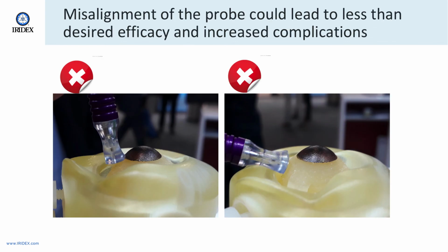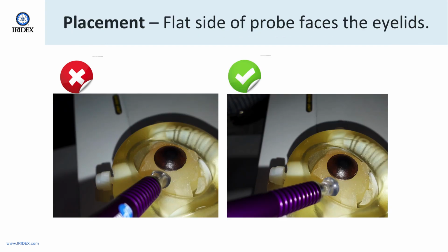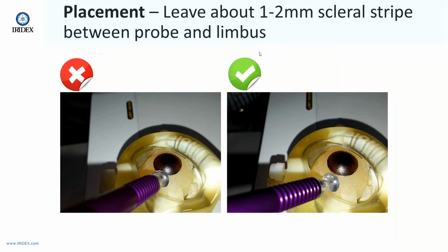Misalignment of the probe could lead to less than desired efficacy and an increase in complications. Orientation or placement puts the flat side of the probe towards the eyelids and the round side of the probe and notch towards the limbus. We want to leave about 1 to 2 millimeters of scleral stripe between the probe and the limbus. And there again, this is imperative to make sure that the alignment of the fiber is over the ciliary body.